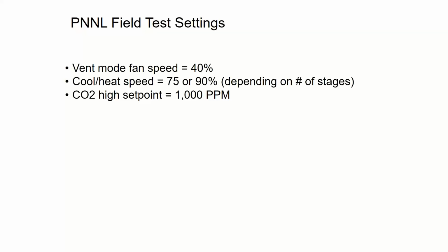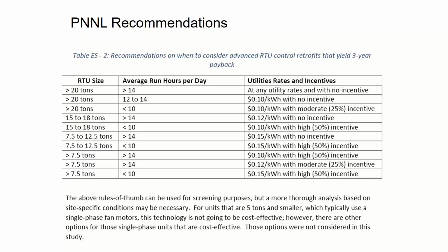At no point in time did they go to 100% of the airflow on any of these 66 units that they studied, because every single unit was so grossly oversized, there was not one that needed the full airflow, which tells you something right there.